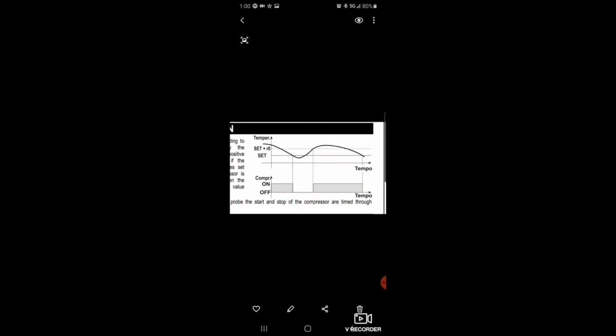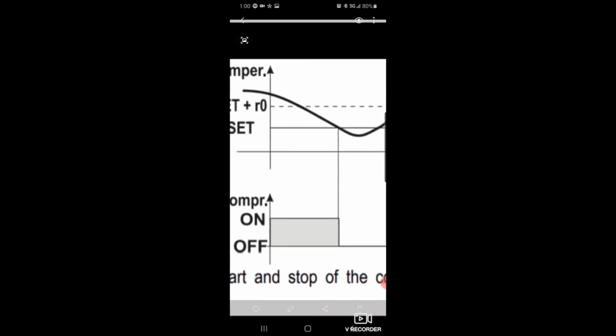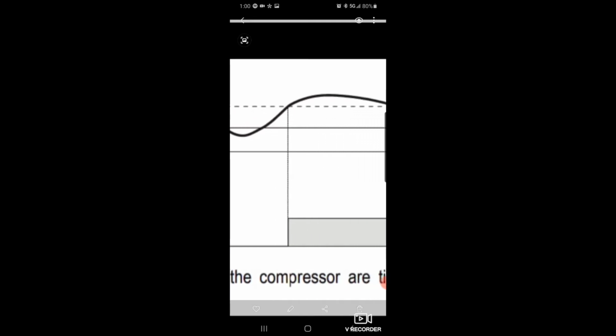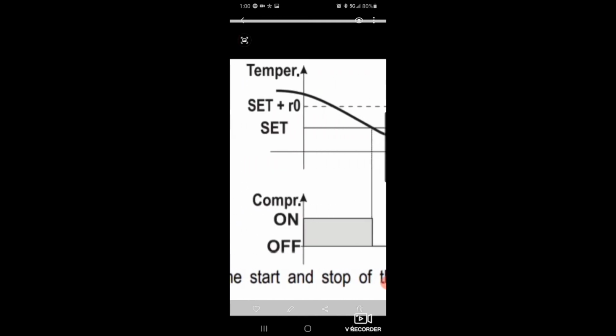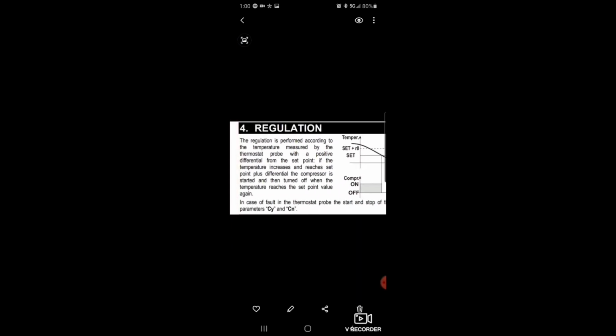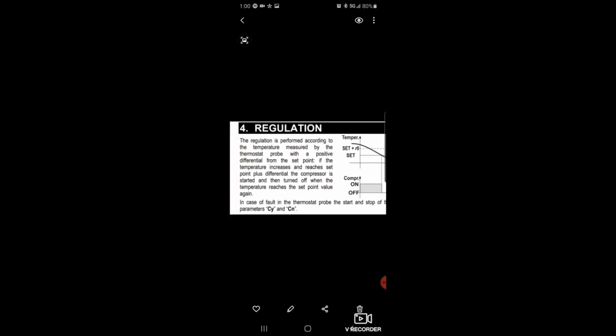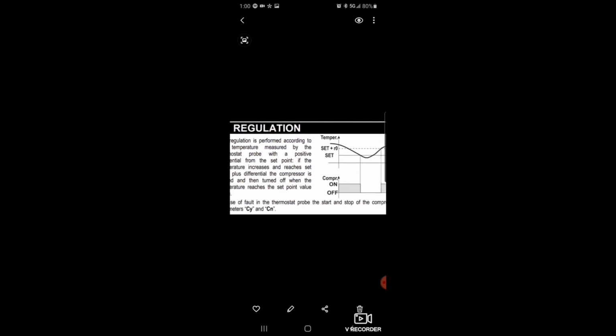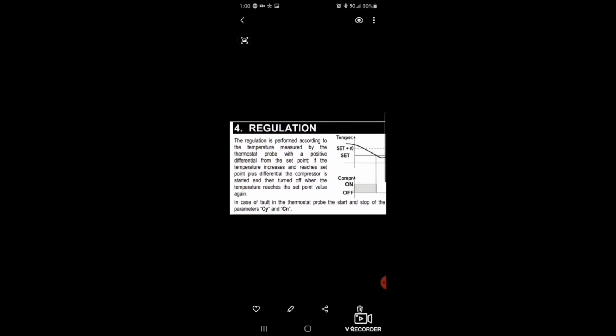And it shows a chart where the top section says set temperature, compressor's running, satisfies, temperature rises, compressor turns back on. Same thing on bottom. And if you read the bottom section, the bottom left, it says in case of fault of the thermostat probe, the start and stop of the compressor are timed through parameters CY and CN. So that's why it's still running. So the compressors are timed now and not running off of that thermostat probe to tell it when to turn on and turn off. So it'll run. It's gonna beep when it goes into that area again.